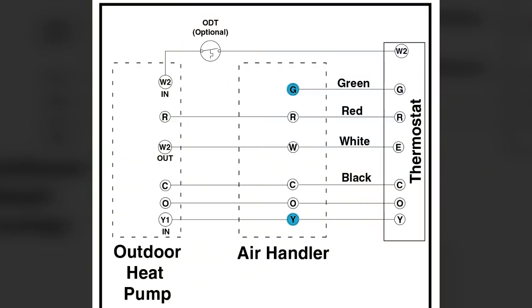G on most units anymore, on a standard blower, is going to energize that blower the same as the heating speed, not the cooling speed. So keep that in mind. And remember, Y is what turns on the heat pump, whether it's in cooling mode or heating mode. W does not turn on that heat pump. Y turns on the heat pump. So one of the other connections we need to discuss a little bit in here that makes it a little different with the heat pump is the W2 and the E terminals and your W2 out and your W2 in on the outdoor unit. Those are the terminals that are a little bit different.